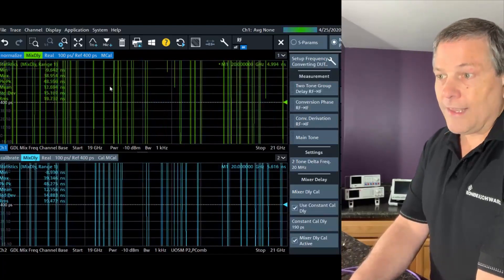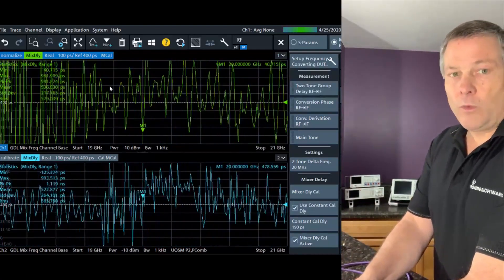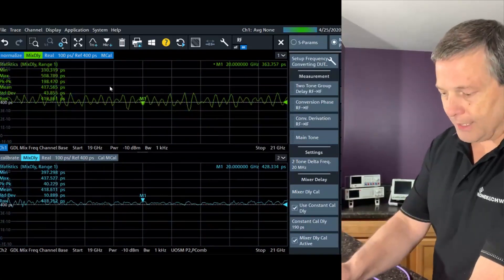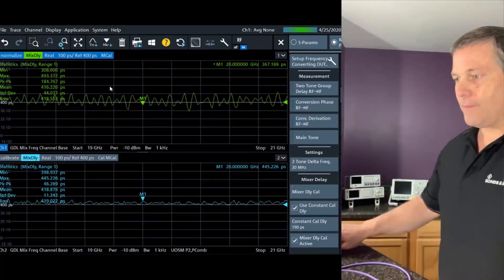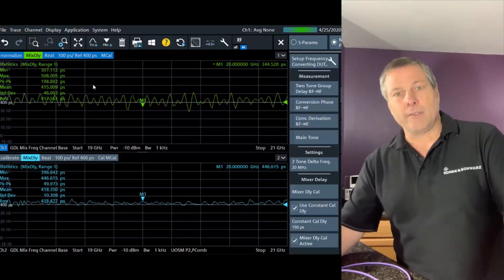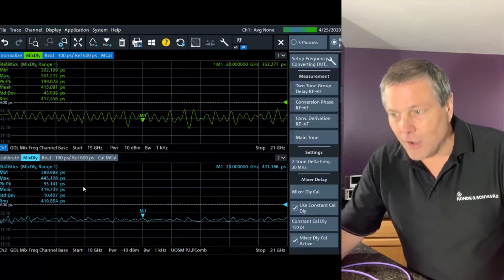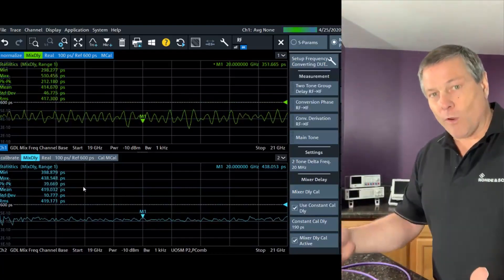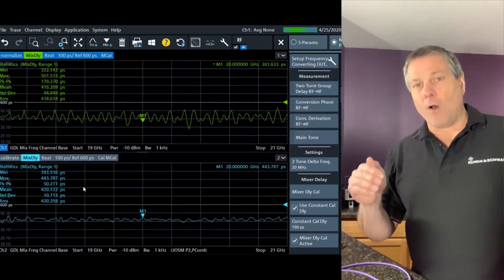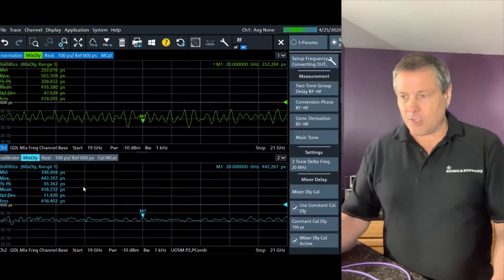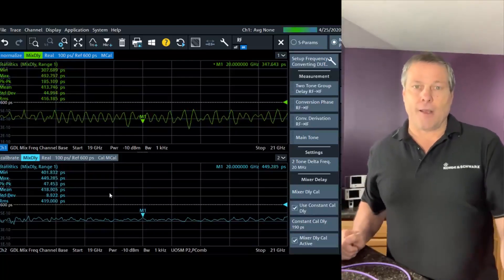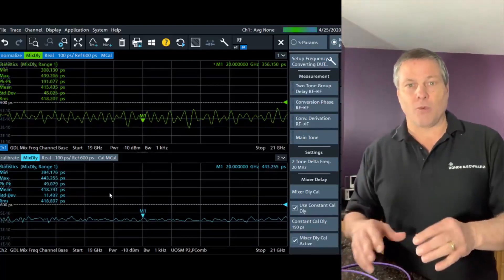At the end of video number 9, on that normalized channel — duplicated here on the top screen — we were very happy with only a few hundred picoseconds of variation, because we had attenuators in place. But now take a look: the top channel still has a peak-to-peak variation of 200 picoseconds, and we were really happy with that just one video back. But the bottom channel, with vector correction applied, has peak-to-peak variation of only 50 picoseconds — another factor of 4 improvement. We now have all the ideas applied, and we're adapting to the new mismatch while still making a very good measurement.